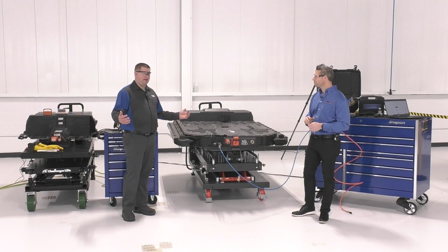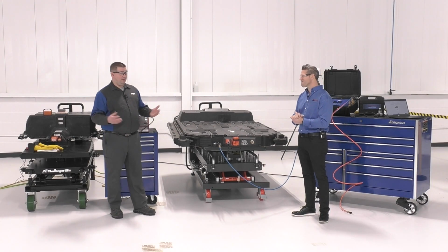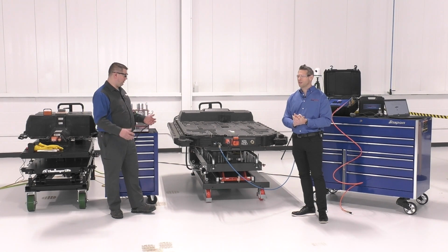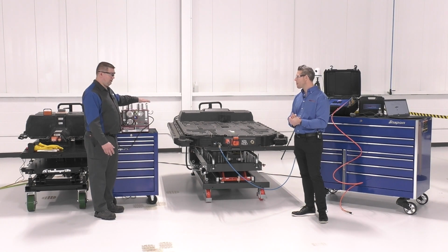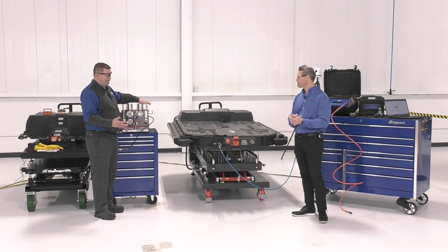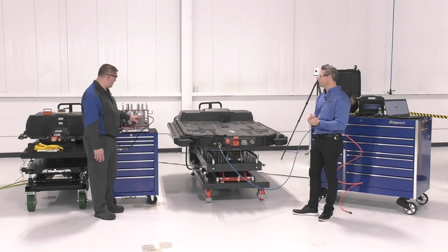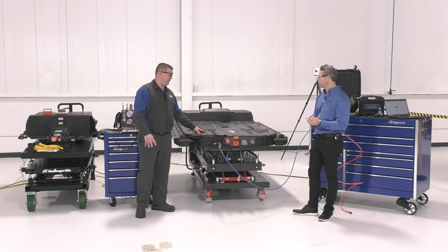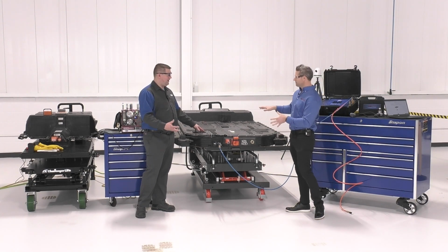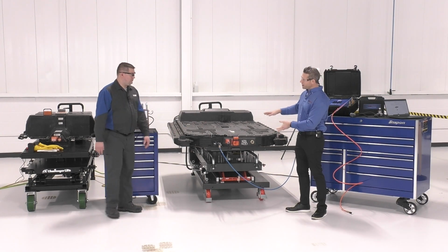That's another great question. Once again, it's all going to depend on how the OEM does it and how the tools work. For example, this one here, we've seen about that 10 to 15 minute range, depending on how long it's taken, for this test to fill this enclosure with half a PSI. Yeah, because the enclosure expands and that type of thing.